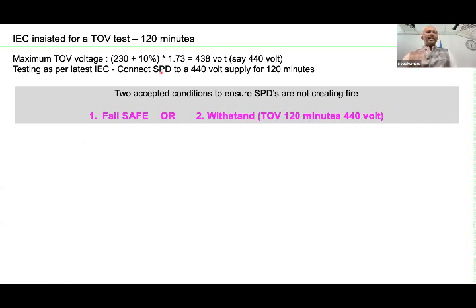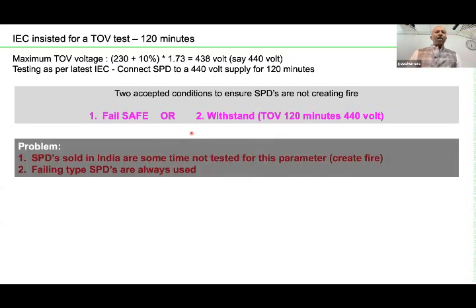So there are 3 cases here. The first is it may explode. The second is it will fail safe, or the third is it is able to withstand. Now only the last two are accepted in the standard. The SPDs which blast, you cannot sell them. So that is unsafe. Now this test parameter has been included a few years back. Fail safe or TOV withstand for 2 hours.